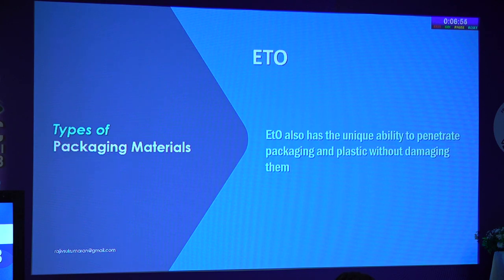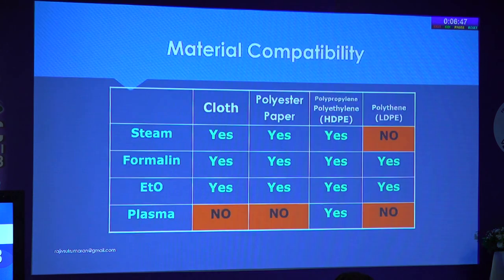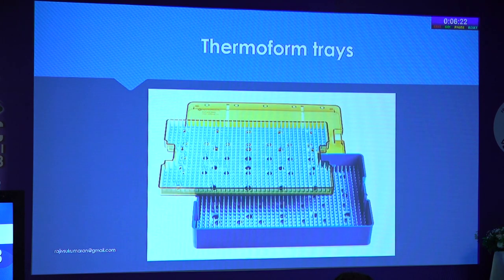ETO has a unique ability to penetrate packing and plastic without damaging them. Regarding materials that can be used: in steam, all materials except low-density polythene can be used. In formalin, all materials can be used, but we are not using formalin in ophthalmology practice anymore. For ETO, all can be used. But in plasma sterilization, only high-density polypropylene can be used — paper and cloth cannot be used.